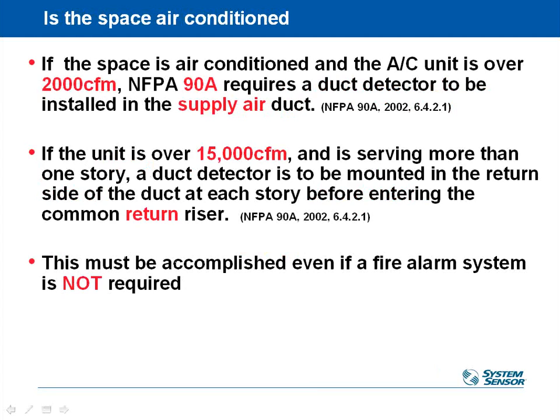All right, so NFPA, National Fire Protection Association Standard 90A, requires that if you have units that are above 2,000 CFM, you have to install a duct smoke detector in the supply air duct. Okay? Supply air duct over 2,000 CFM required. Additionally, if you've got a unit that's more than 15,000 CFM and is serving more than one floor of the building, so you've got a 50-ton rooftop providing air conditioning to 2 or 3 floors, then you have to have a duct detector mounted in the return duct at each story before it goes into the common return riser. So if you had a 50-ton rooftop serving 2 floors, you'd have 3 detectors. 1 in the return duct for each floor, and then 1 in the main supply duct.